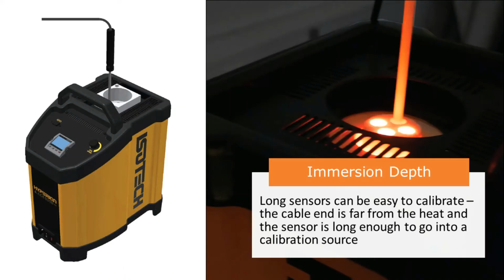Long sensors can be easy to calibrate. The cable end is far from the source of heat, and the sensor is long enough to go into the calibration source to a suitable immersion depth.